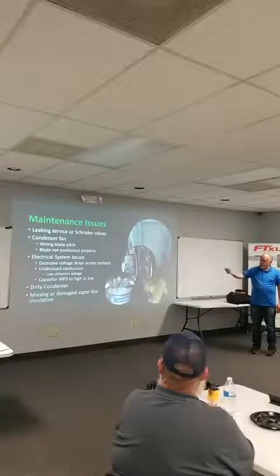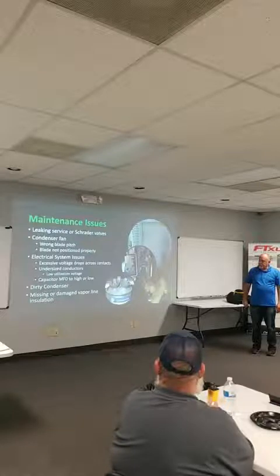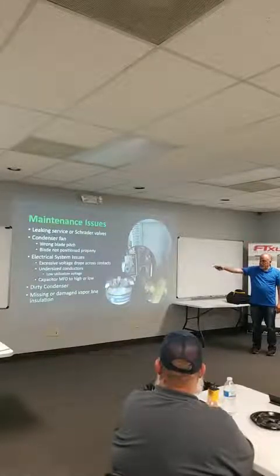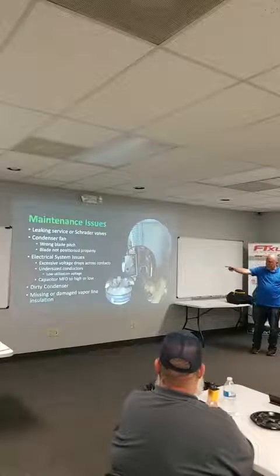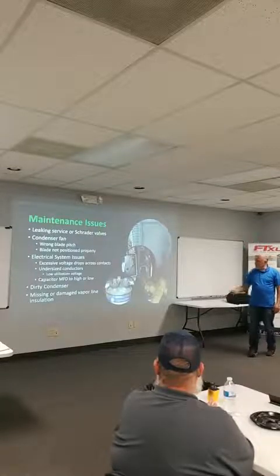Electrical system issues: excessive voltage drops across contacts. There's no standard for this, but when you start seeing the contacts look pitted like this, they're probably due to be replaced. Dirty condensers, capacitors, those kinds of problems.